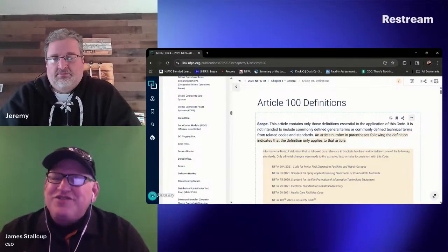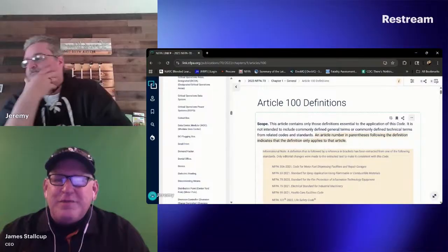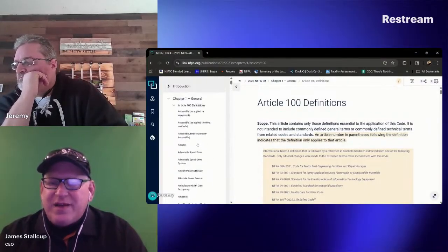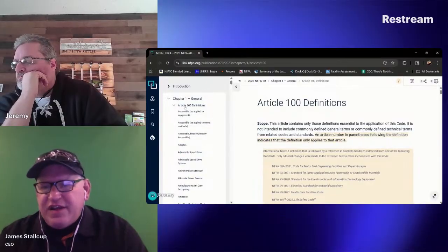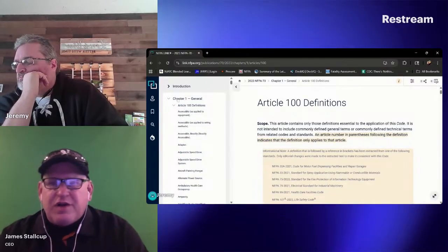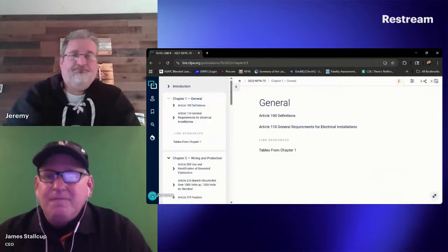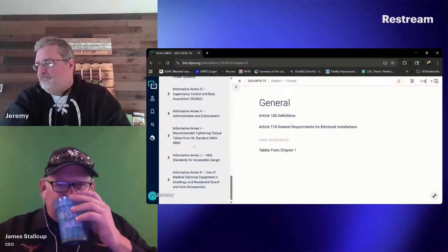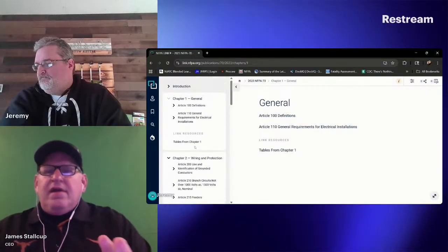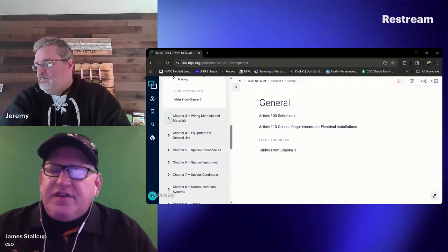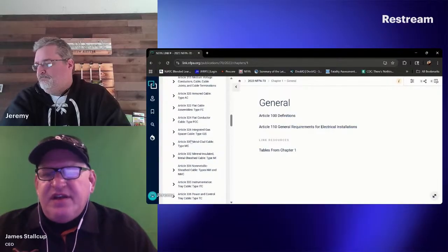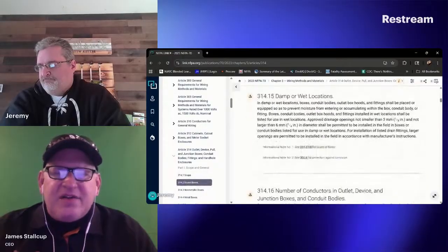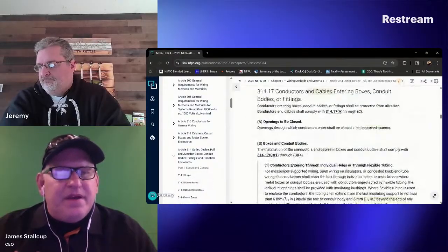You got your question. So I'm going to take you back over here, and we're going to look at 314.27 again. I'm going to show you how ridiculous this sounds, what y'all are trying to say. If I look at a box and I have a ceiling outlet, it says at every outlet used exclusively for lighting, the box shall be designed and installed so that a luminaire can be attached.